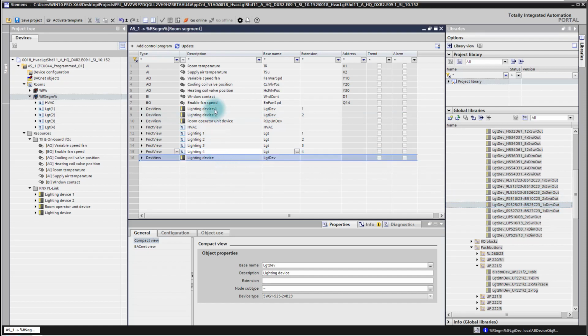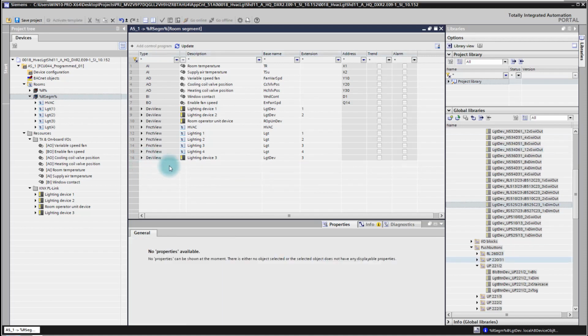That's now this one here, and as we had already 2 lighting devices in, we give it the number 3. So this number 3 is now indicating not the lighting group itself, it indicates the device number 3. This is for better separation later on in our system. In the device number 3, we have here an output which we apply to lighting group number 5. So that is the setup of the output device. We will do the same now also with the push button device. Here for an example we use also an additional one.